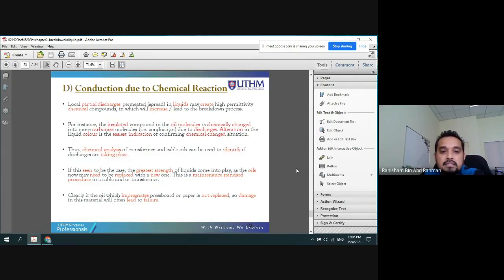The last mechanism is conduction of electric charge due to chemical reaction. For example, we have liquid with different permittivity, different chemical compounds, and different properties. This usually leads to failure of the insulator. For example, oil molecules can chemically change into more carbonized molecules. Once we have carbonization, it becomes easier for current to flow, meaning the carbon will trigger or promote current conduction due to the discharge activities.